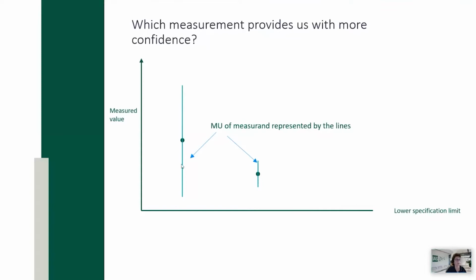So assuming that the measurement uncertainties are evaluated correctly and have taken all the significant factors into account, we can decide which one might be a better measurement, and we can decide that better if we know the measurement uncertainty around it. So this is really an illustration of how your result is really incomplete if you don't know the measurement uncertainty that's associated with it.